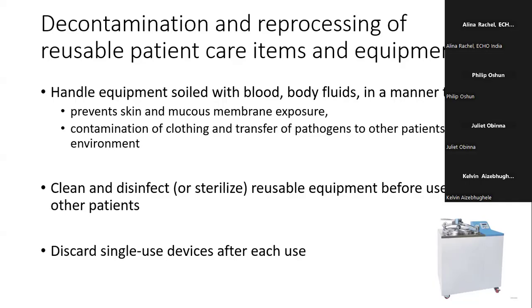For reprocessing or decontamination, the first step is to clean—that's why we say cleaning, disinfection, and or sterilization. So the first step to disinfection, sterilization, or reprocessing of a medical device is to clean, so that we can remove debris and remove organic matter.